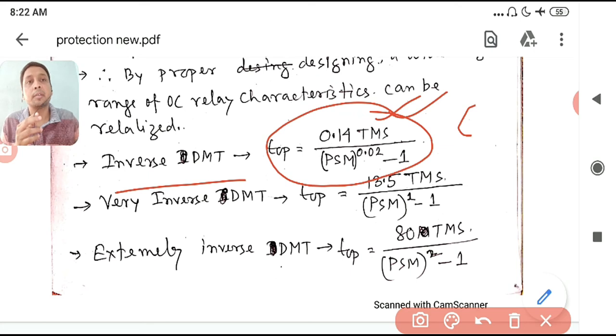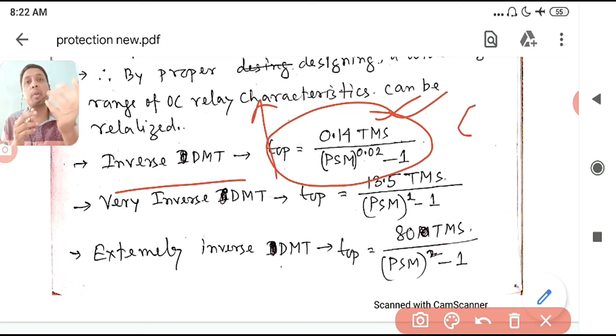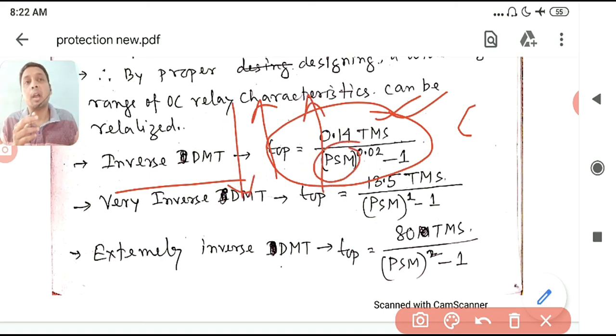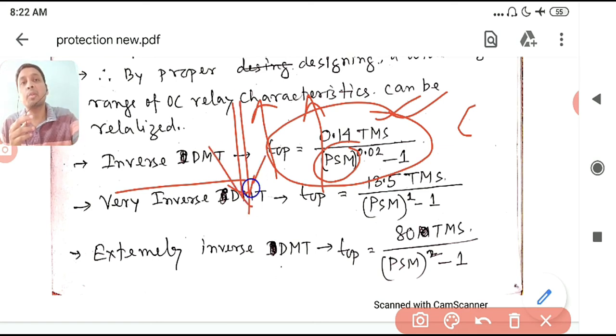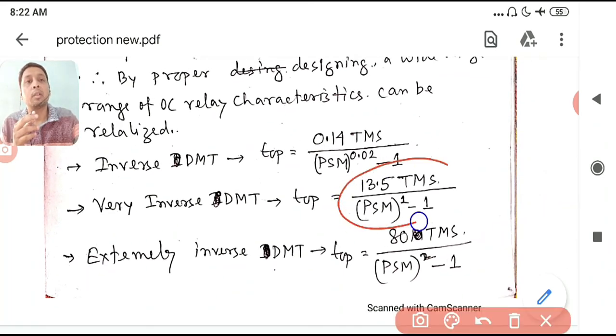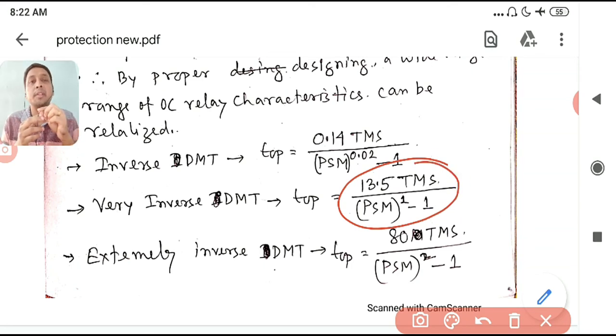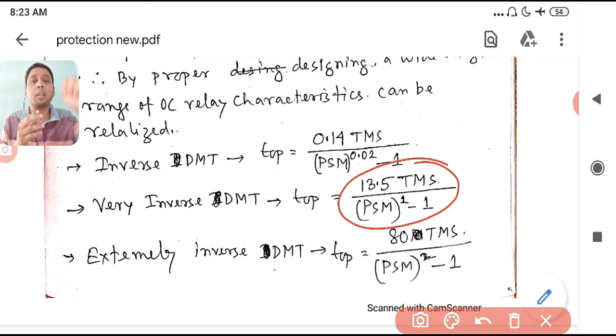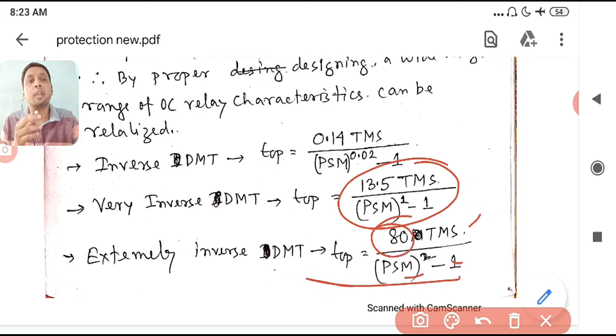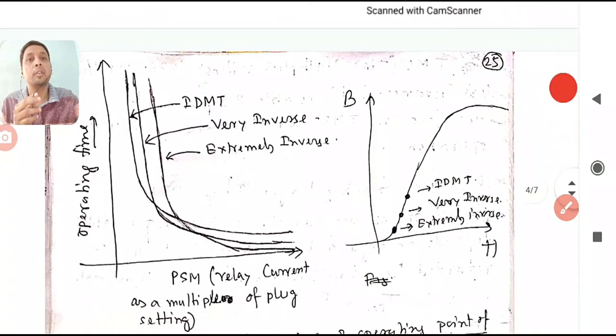For Normal Inverse (IDMT), if TMS increases, operating time increases — you are moving the disc farther from the trip contact. If PSM increases (more severe fault), operating time decreases. For Very Inverse, the constant values are larger — for higher current, the operating time is even lower compared to Normal Inverse.